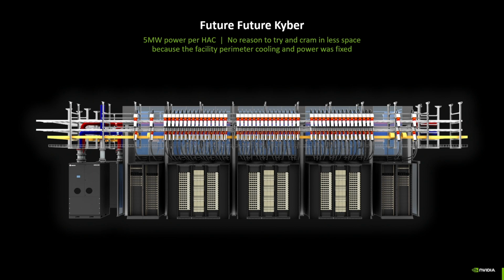So I went from a hot aisle containment that had 24 racks, 4 in the front, 4 in the back, times 3. As power went up, I cut the racks in half. As power goes up again, I go from 8 racks to 1 high power rack. So what you see pictured here is some theoretical future with 3 high power racks, and there are power sidecars that actually shim in between the data center power and the Kyber rack.